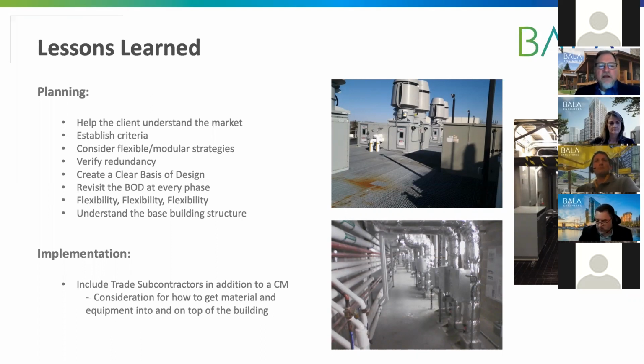Verify how much of it needs to be flexible, because I may be doing a flex space where I'm putting in one set of labs day one, but the infrastructure sized for day two, with another set coming in. Or how much is going to be modular so we can drop in pre-manufactured clean rooms and things like that. And what's our redundancy requirement?